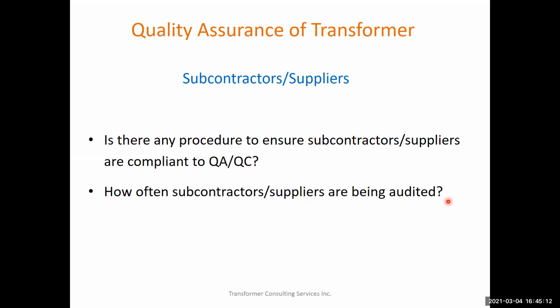The second problem is the core. I showed you a picture of pre-cut core steel earlier. If the factory is located in, say, London, UK, and the core steel comes from Italy by ship, it may not be packaged properly or oil-soaked during transit. During that process, the quality of the steel can be compromised. So this outsourcing, and how well the manufacturer maintains subcontractor quality, is becoming an issue that compromises transformer quality.